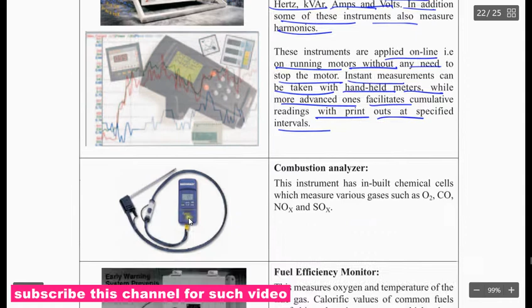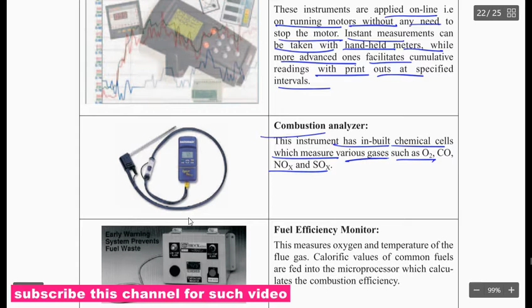Instant measurement can be taken with the handheld meter while motor is on, facilitating cumulative reading with printout at a specific interval. And combustion analyzer. This instrument has inbuilt chemical cells which measure various gases such as O2, CO, and NOx, nitric oxide, and sulfur oxide. And fuel efficiency monitor. This measures the oxygen and temperature of the flue gas, and calorific values of the common fuels are fed into the microprocessor which calculates the combustion efficiency.